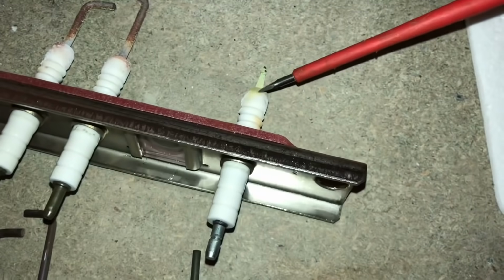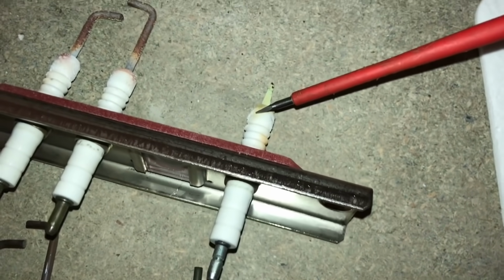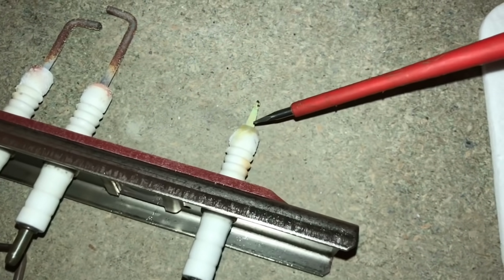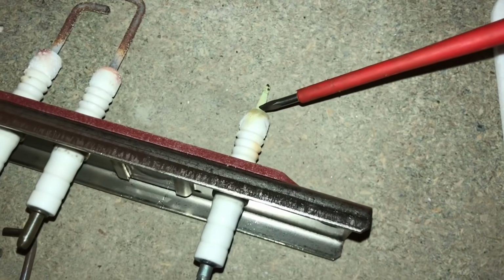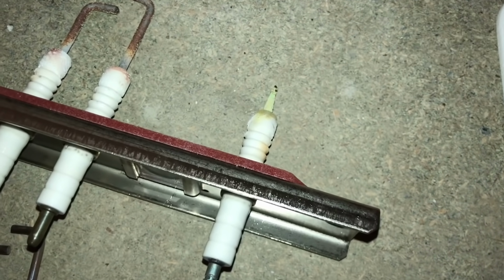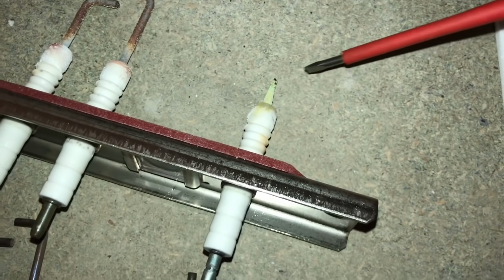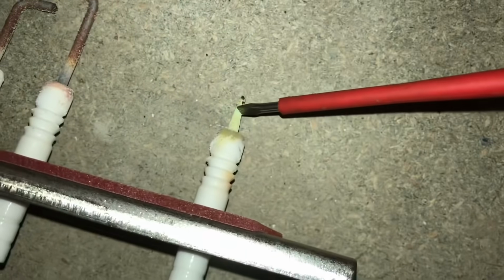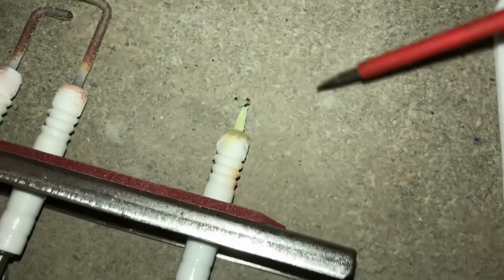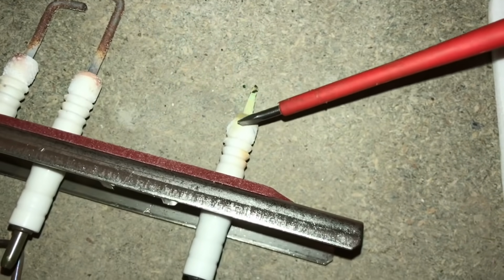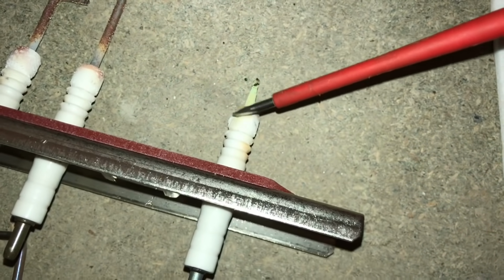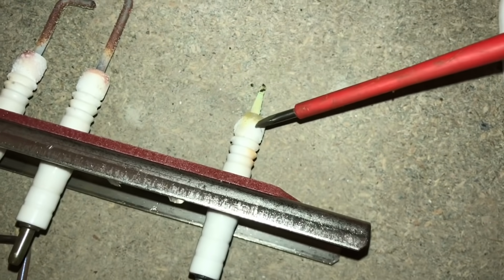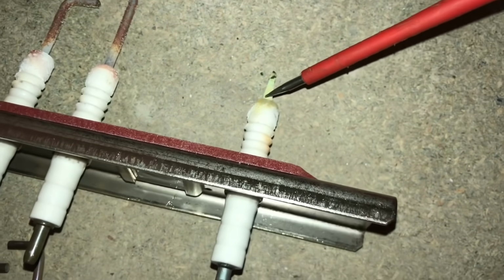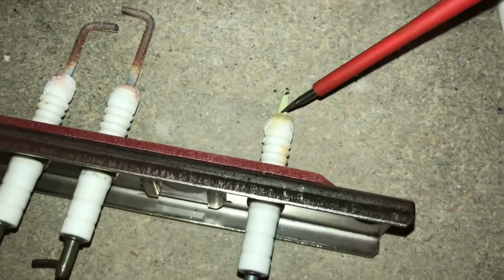This is the rectification probe. So this basically senses, once the gas is lit, sends a message down to the gas valve on the circuit board, so yeah, the flame's lit, you can go into full fire mode. And you can see on the end there, it's worn down to a fine point. This is really common on LPG boilers because they burn at a hotter temperature. But the reason this one's like this is because it's never been serviced or looked at since it was installed.